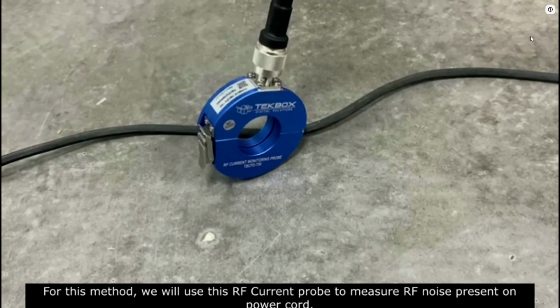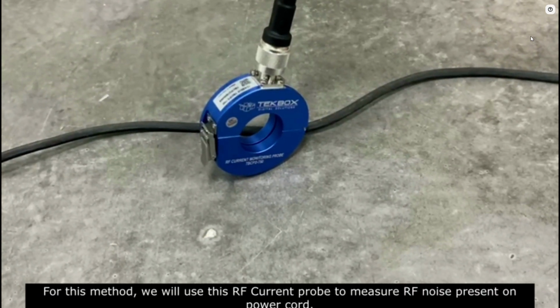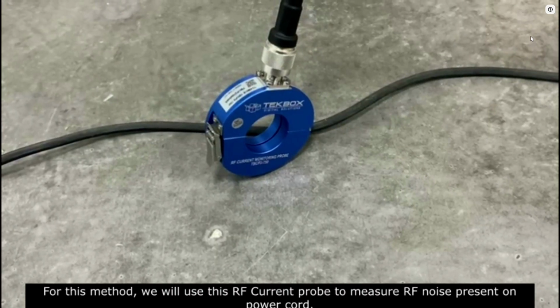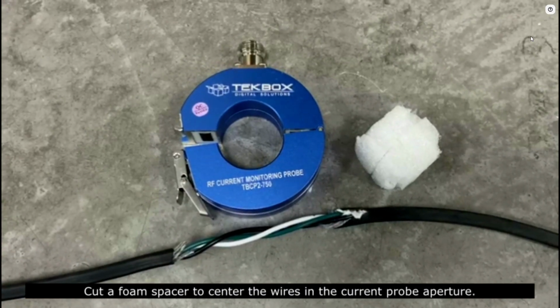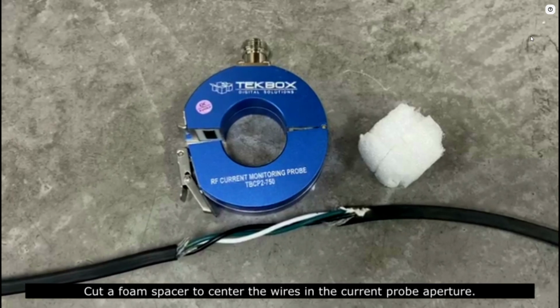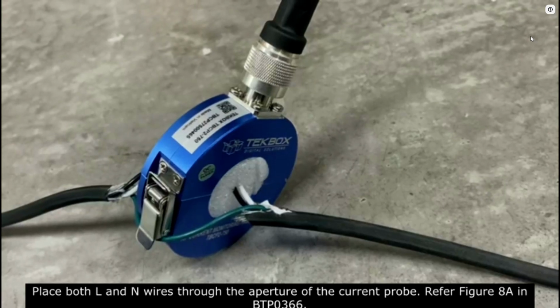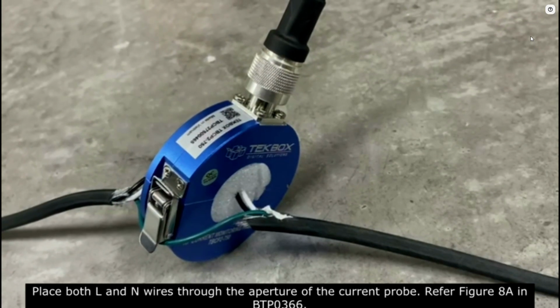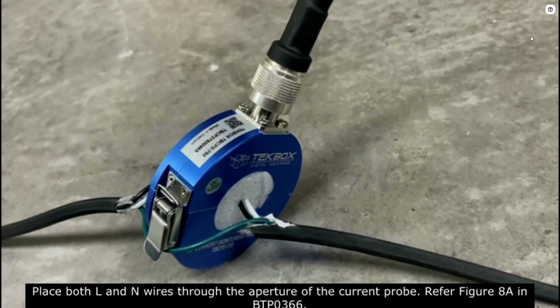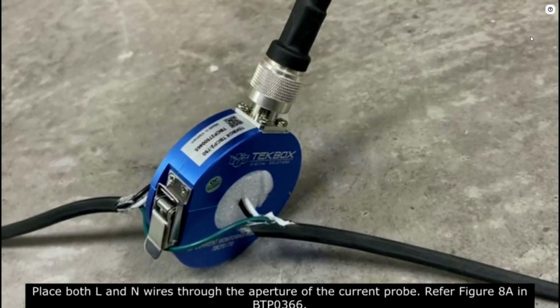For this method, we will use this RF current probe to measure RF noise present on the power cord. Cut a foam spacer to center the wires in the current probe aperture. Place both L and N wires through the aperture of the current probe. Refer to Figure 8A in BTP 0366.